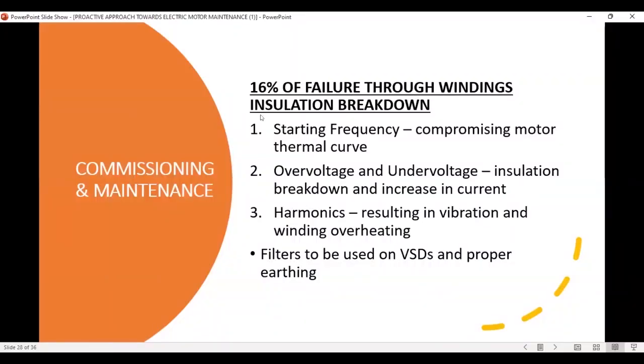16% of motor failures are through insulation breakdown. So the starting frequency must always be checked. Motors come with a number of starts per hour, so you check and insert it into your motor protection relay. For the smaller motors, we must ensure that we also check the number of starts. If you start a motor and it was overloaded and it tripped, you must wait for it to cool down before you restart again. So put in the right parameters and it will restrict operators from misusing the motors.